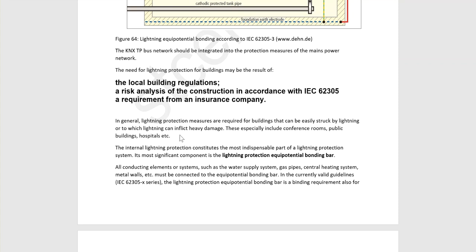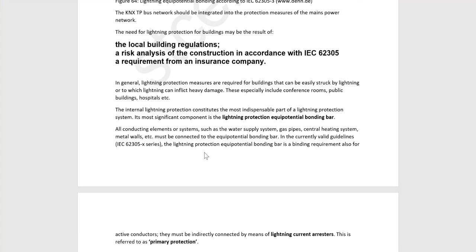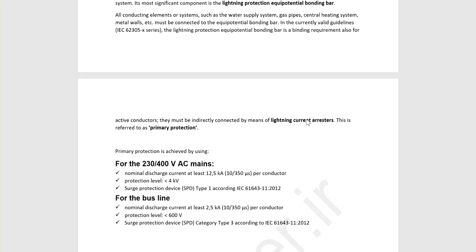In general, lightning protection measures are required for buildings that can be easily struck by lightning or to which lightning can inflict heavy damage. These especially include conference rooms, public buildings, and so on. So if you are in a big or very big project, of course you face lightning protection and you should consider something in KNX. The internal lightning protection is the most indispensable part of the lightning protection system. Its most significant component is the lightning protection equipotential bonding bar. So we have the bonding bar in lightning protection, of course.